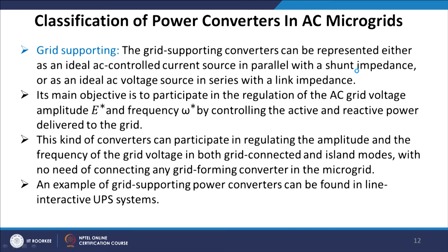The grid supporting converter can be represented either as an ideal AC controlled current source in parallel with a shunt impedance, or as an ideal AC voltage source in series with a link impedance. Its main objective is to participate in the regulation of AC grid voltage amplitude E and frequency omega by controlling the active and reactive power delivered to the grid. This kind of converter can participate in regulating amplitude and frequency of grid voltage in both grid-connected and islanded modes, with no need for connecting any grid forming converters. An example of a grid supporting power converter can be found in line-interactive UPS systems.